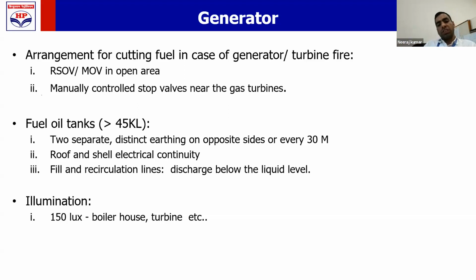To avoid generation of static electricity in your fuel oil tank, you should provide discharge, fill and recirculation lines discharging below the liquid level. The lux level requirement for the turbine area, for the generator area, is 150 lux. This is so that in case of fire, people should be able to locate firefighting equipment and use it effectively. The minimum requirement is 150 lux for the turbine area.